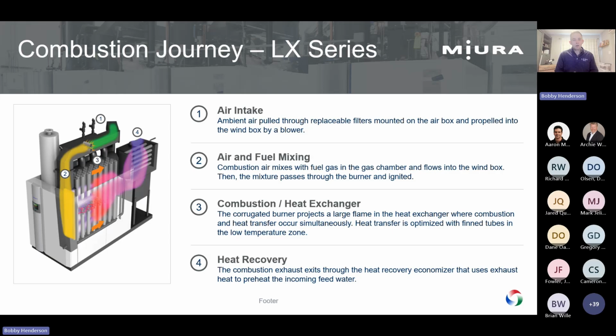Okay, so real quick, this is the Miura LX once through design right here. So this is the combustion journey, the fireside journey. Air is going to come down through the blower and go through these vertical water tubes. It's called a floating header design. So as those tubes expand and contract with heat, the whole thing is going to float together. So it really reduces the stress on the metal within that heat exchanger.